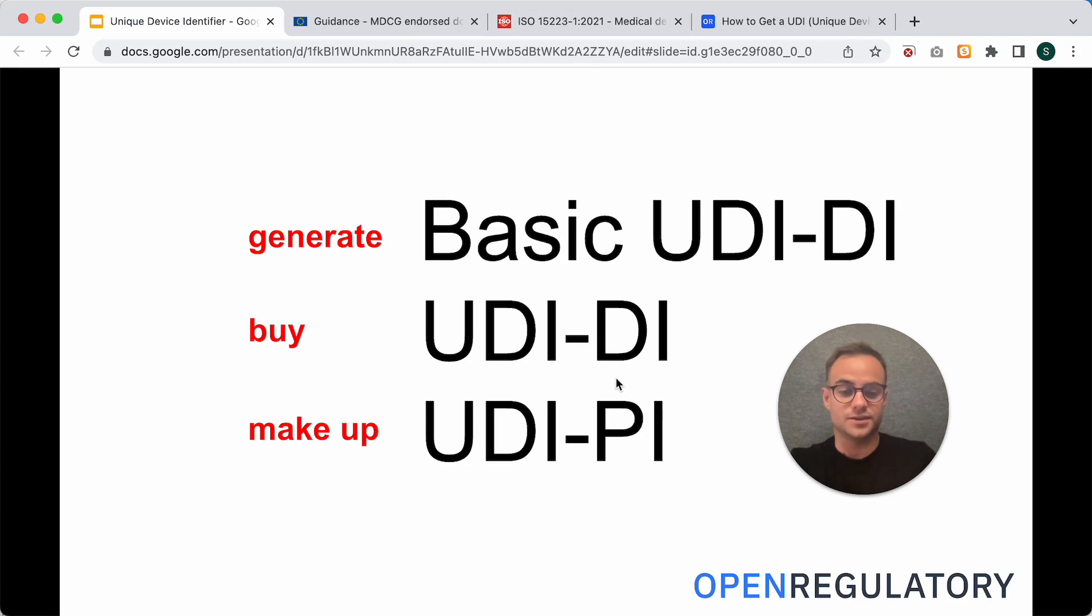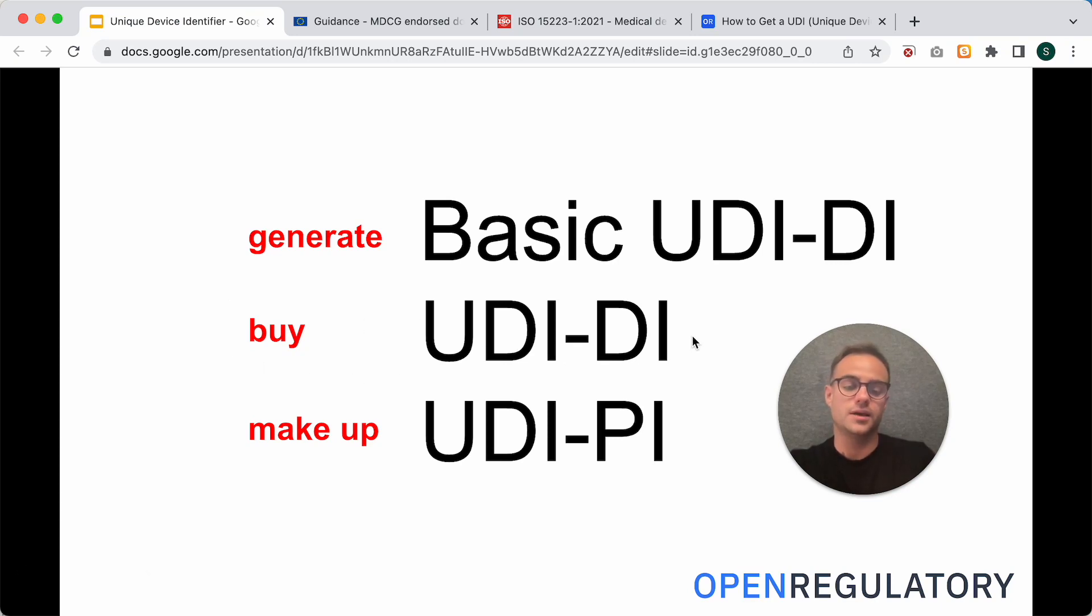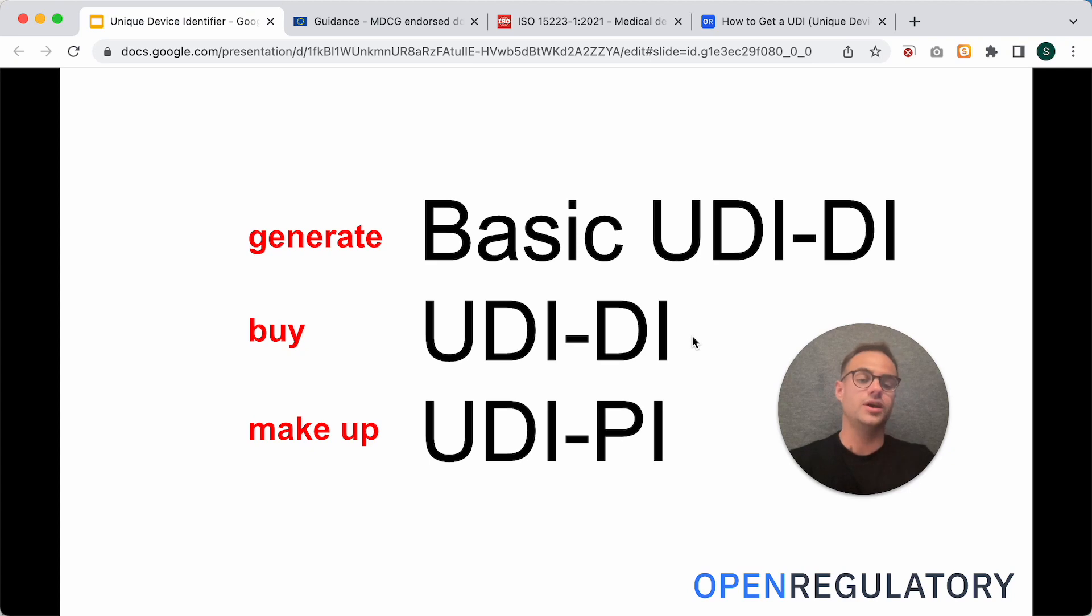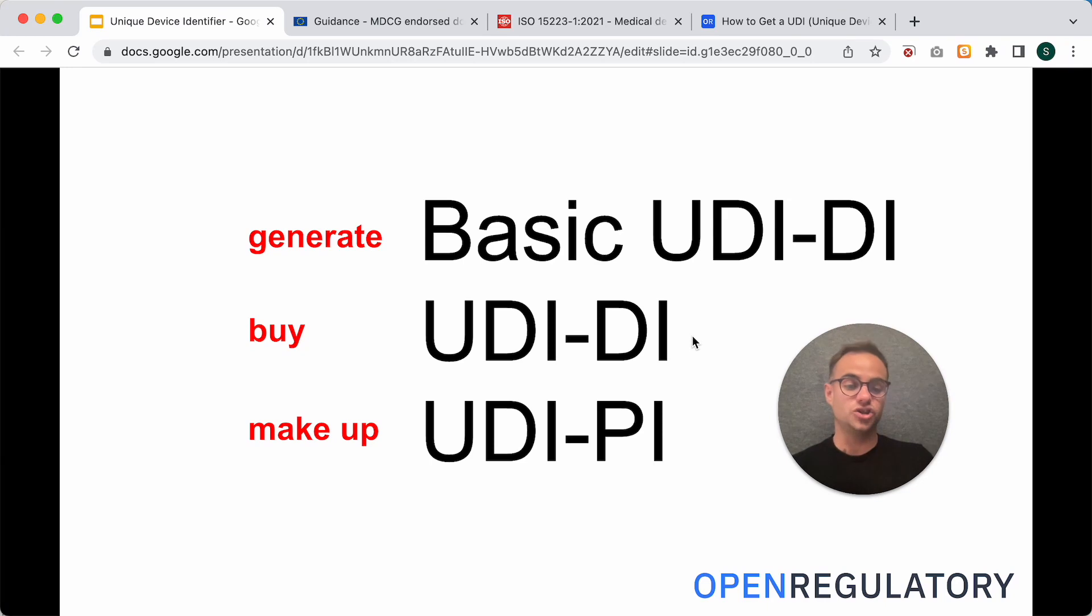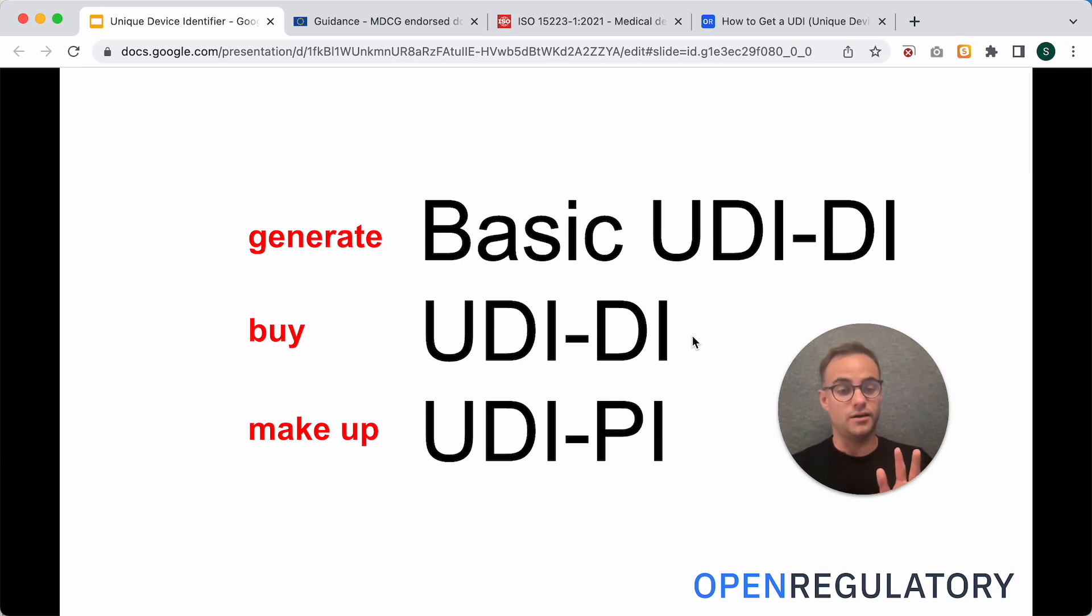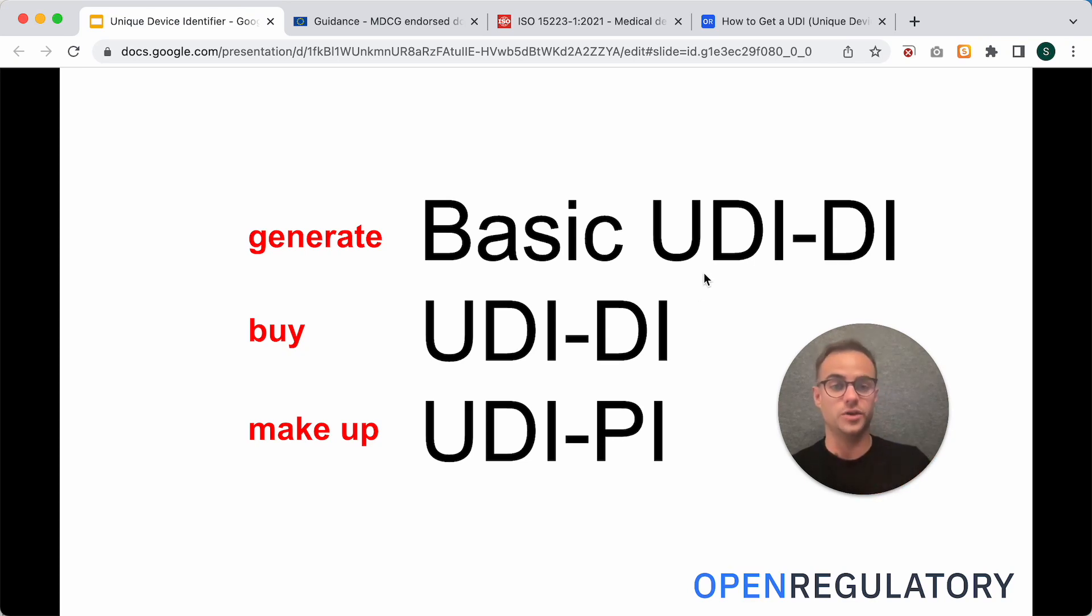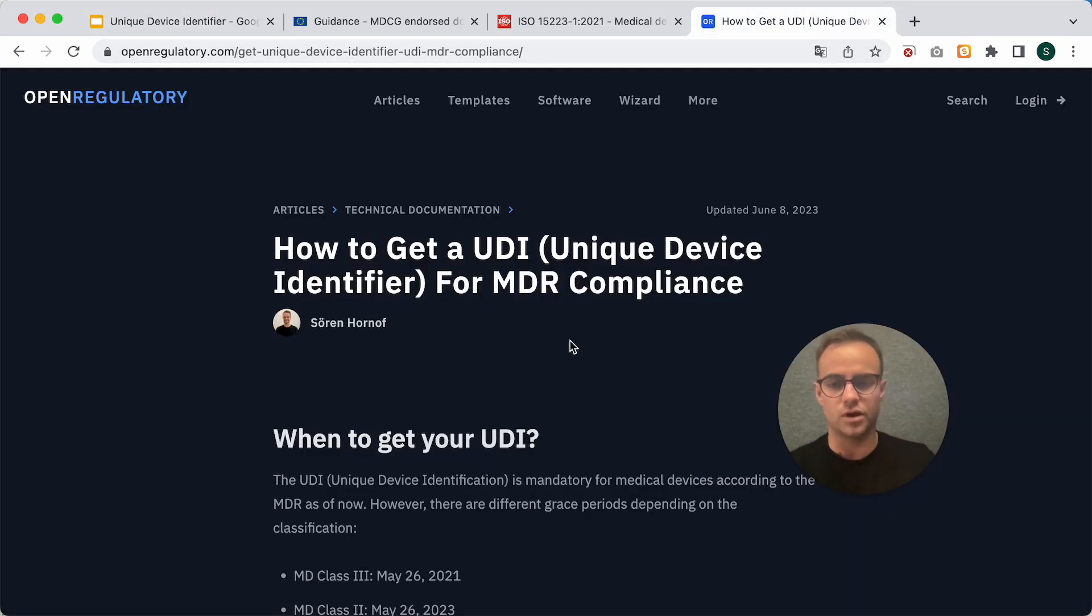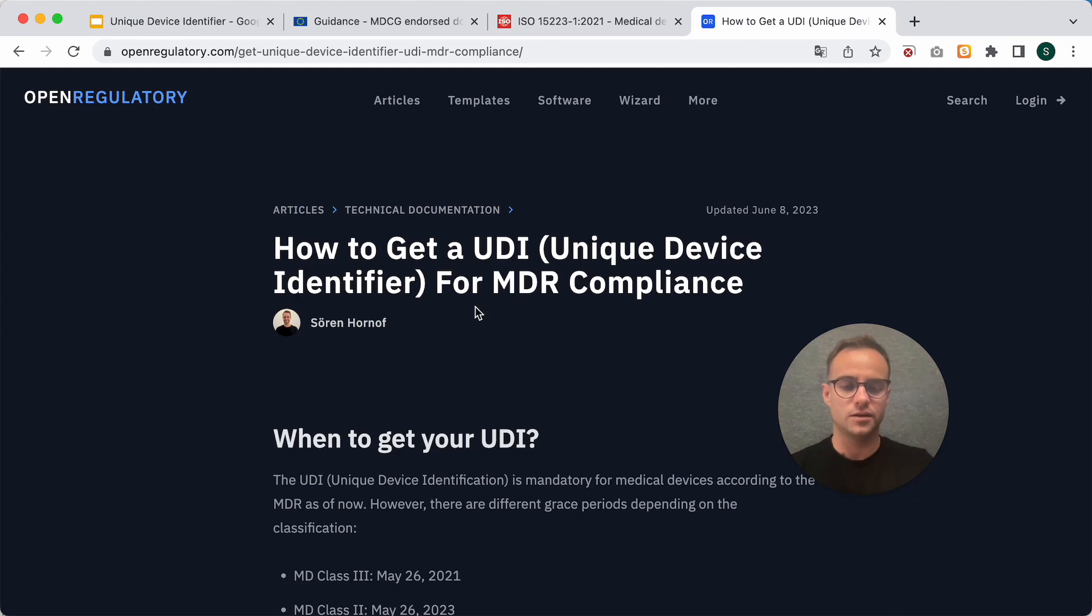So, let's start at the beginning. How and where do you buy this UDI-DI? You can, unfortunately, not buy it from the European Commission or from some other official place, but you actually need to register with a private company that issues numbers. There are four of them that are currently accredited by the European Commission, and I've listed those in an article that I wrote on our website on openregulatory.com. The article is called How to Get a UDI.